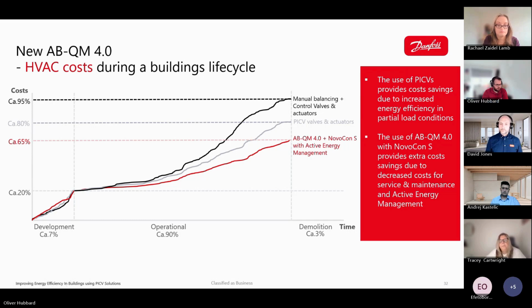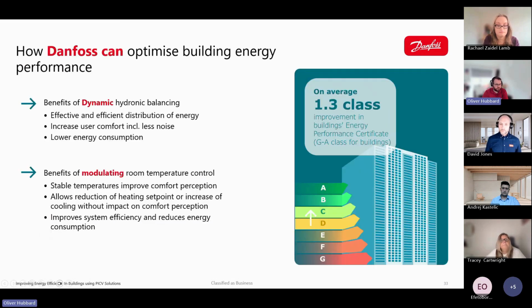So dynamic hydronic balancing ensures energy is distributed efficiently throughout the building and boosts user comfort with quieter operation, and reduces overall energy consumption. Modulating room temperature control maintains stable comfortable indoor temperatures and lets you lower heating or increase cooling set points without affecting the comfort. And this therefore enhances the system efficiency and helps save energy.